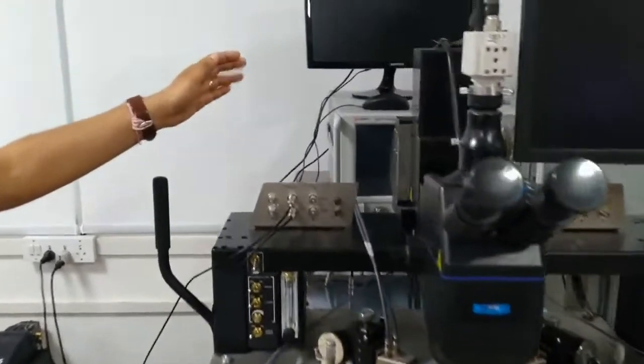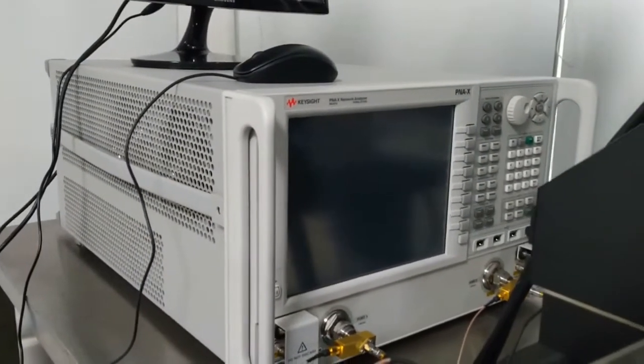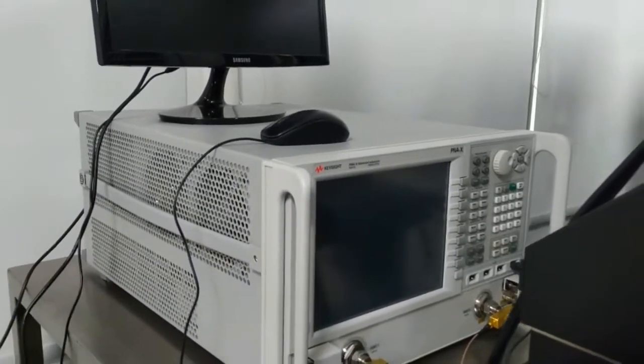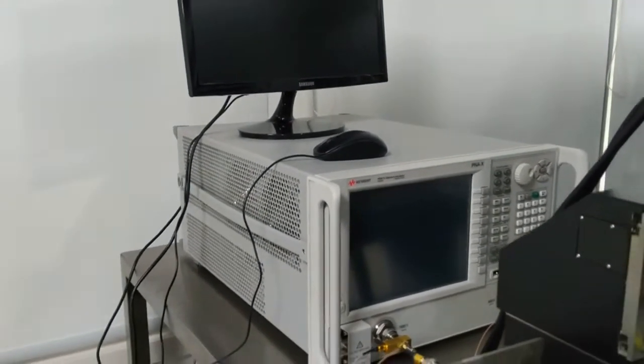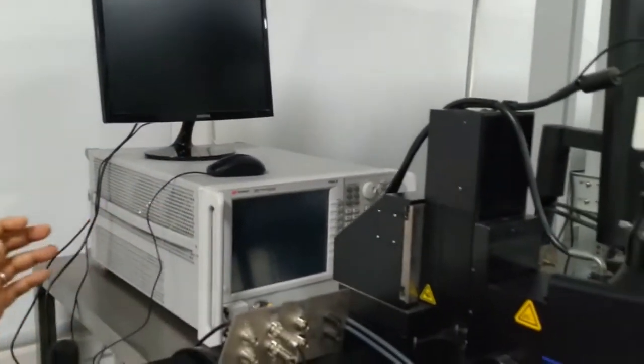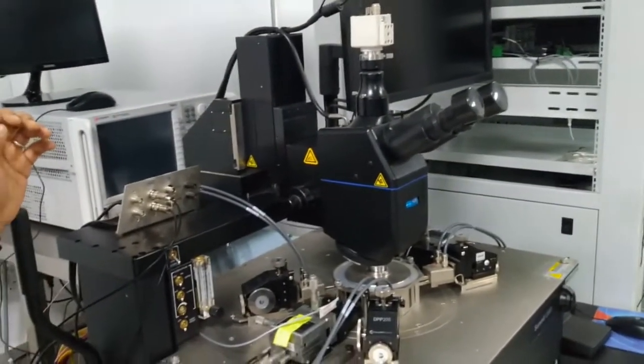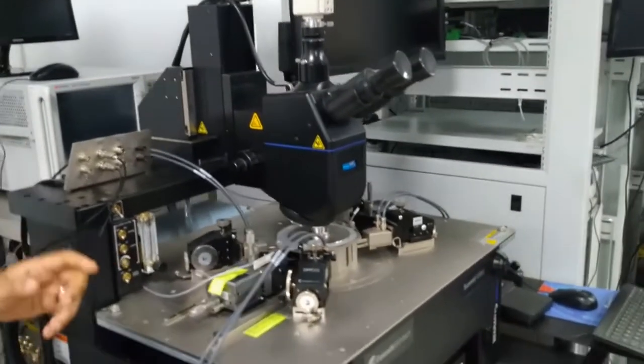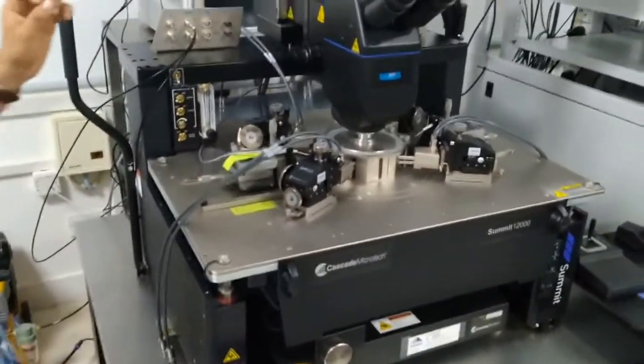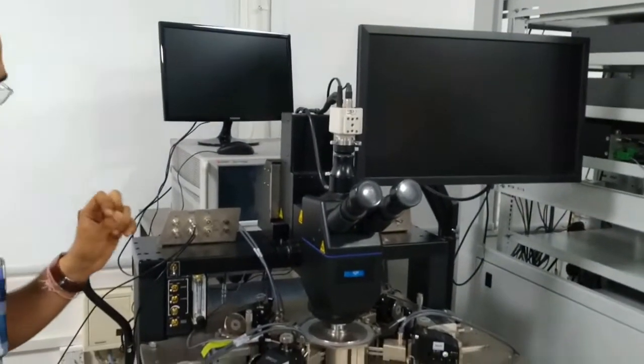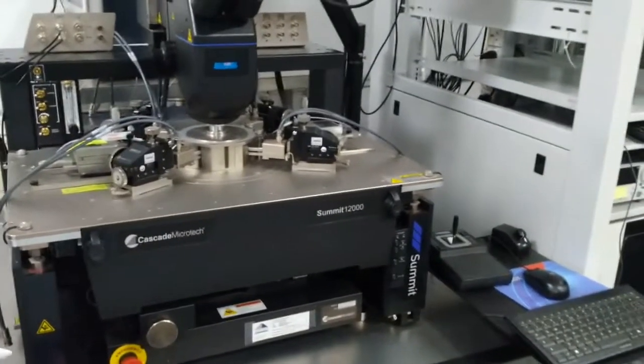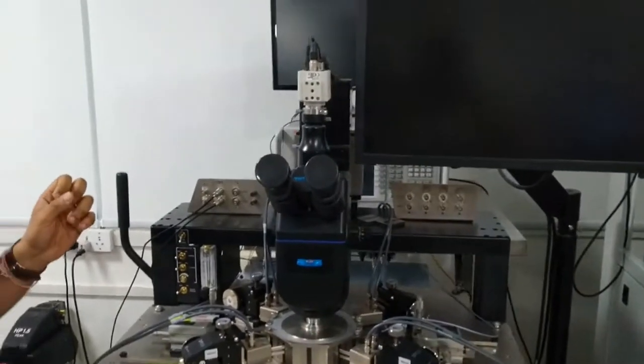We also have a dedicated RF setup which enables us to carry out linear and non-linear RF measurements over a wide range of frequency from 10 MHz to 67 GHz. It is equipped with two internal signal sources, a signal combiner, S-parameter and noise receivers, pulse modulators, generators and flexible set of switches and RF access points. This RF setup allows us to carry out pulsed RF measurements with minimum 20 nanoseconds pulse widths. It provides high frequency resolution capability over as low as 1 Hz with an accuracy of ±1 parts per million. The overall setup reduces test time significantly and allows us to carry out efficient large wafer scale measurements.